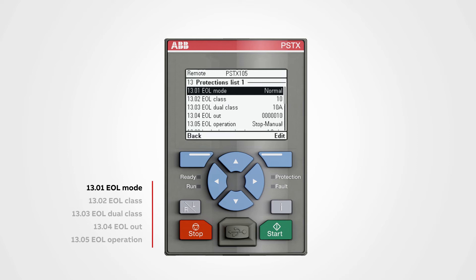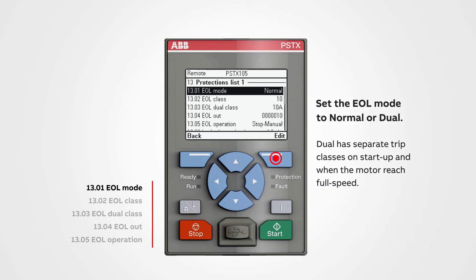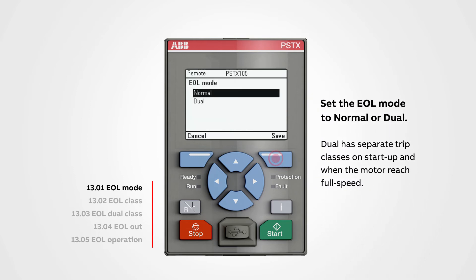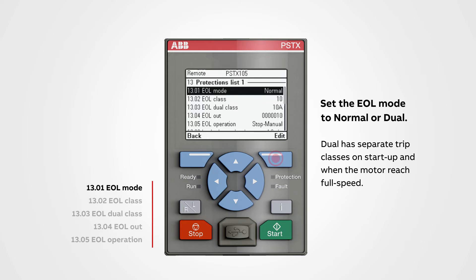EOL mode: set the EOL mode to normal or dual. Dual has separate trip classes on startup and a different one when the motor reaches full speed.